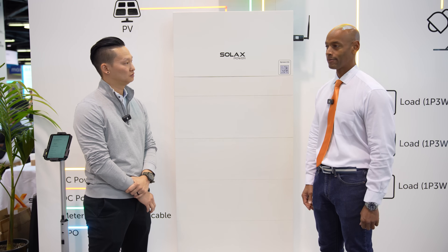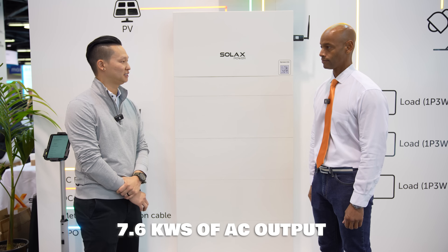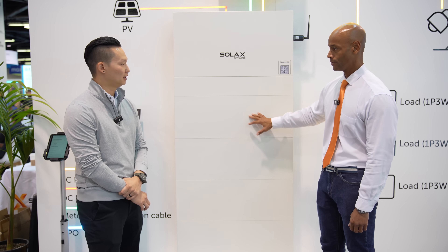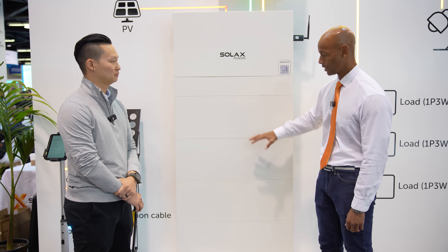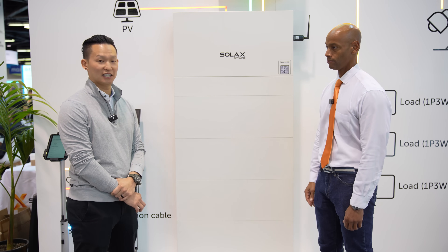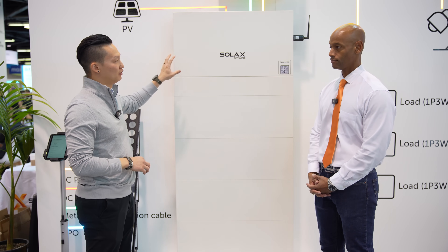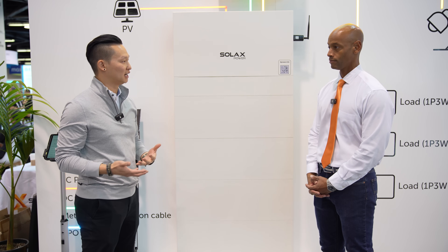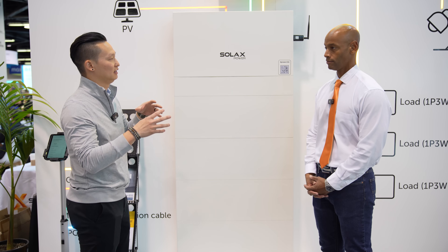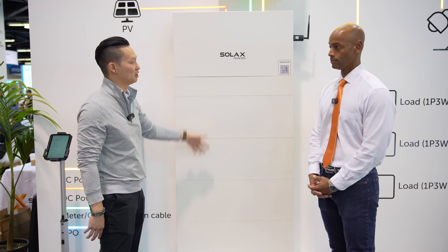A lot of the audience is going to want to know about capabilities. The power output is 7.6 kW AC output. Each battery module is 5 kWh, with about 4.5 kWh usable. For a complete stack with all four modules, that's 20 kWh nameplate and 18 kWh usable. When we look at this inverter itself, we actually allow for 150% oversize on the PV side. What that does is allow us to use about 11.4 kW of power from PV generation, so we can power your home with 7.6 kW and have a couple of kilowatts left over to charge the batteries simultaneously.